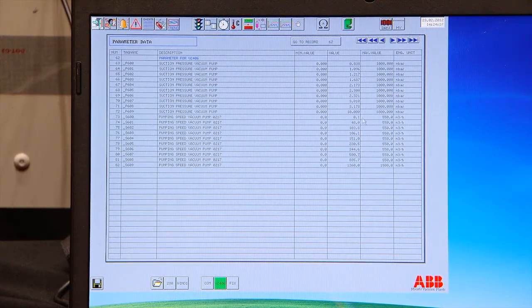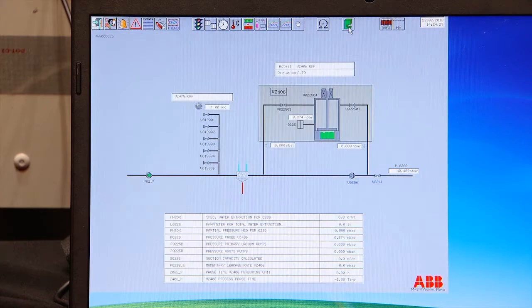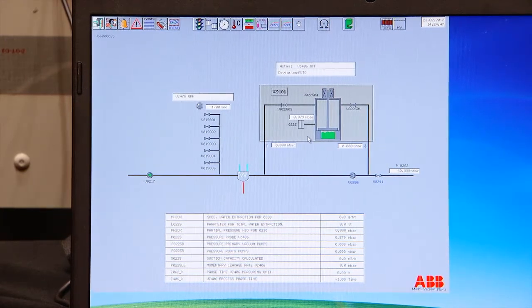What you're missing is that when we are running the 406, we are running at different vacuum levels. Depending on which vacuum level we are running, the vacuum pump has different suction capacity. This suction capacity affects our reading in the chamber. So it did 5 different readings to give different ranges. He's interpolating the pump curve. We have 10 points.